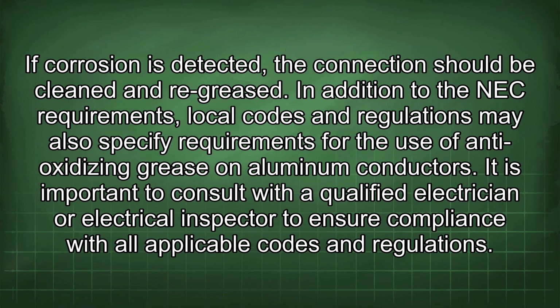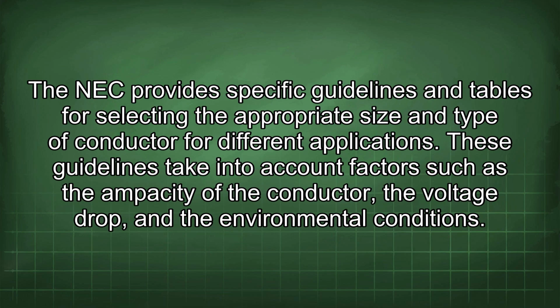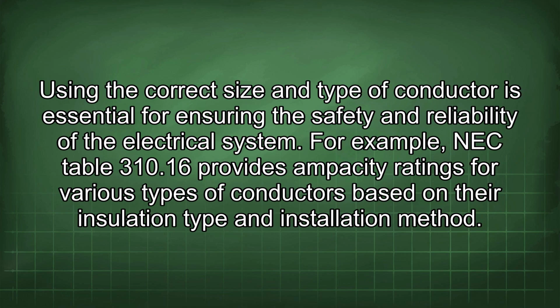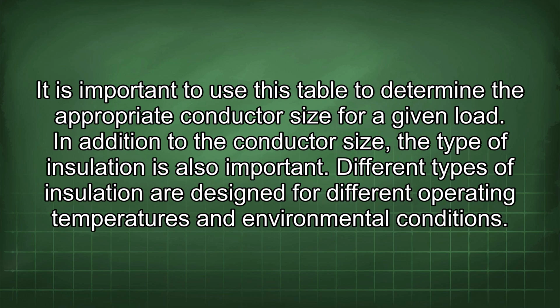The NEC provides specific guidelines and tables for selecting the appropriate size and type of conductor for different applications. These guidelines take into account factors such as the ampacity of the conductor, the voltage drop, and the environmental conditions. Using the correct size and type of conductor is essential for ensuring the safety and reliability of the electrical system. For example, NEC Table 310.16 provides ampacity ratings for various types of conductors based on their insulation type and installation method.